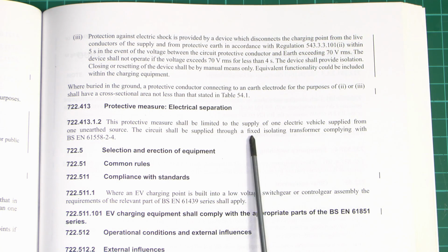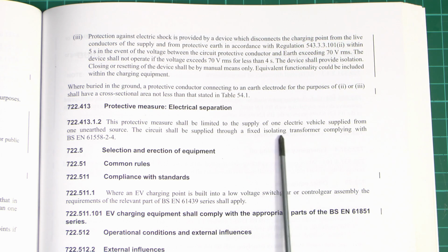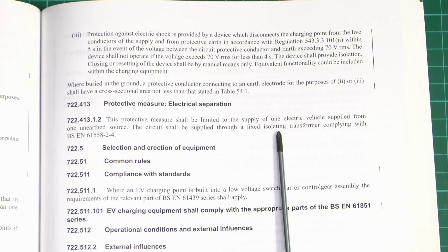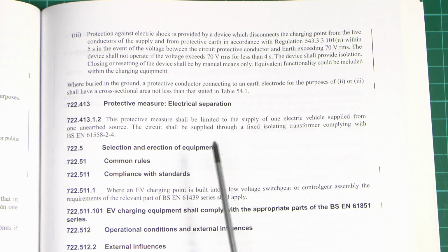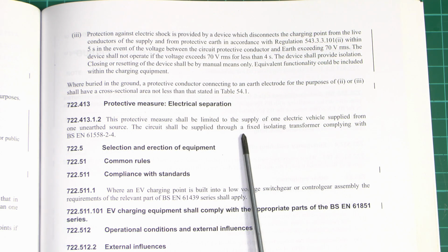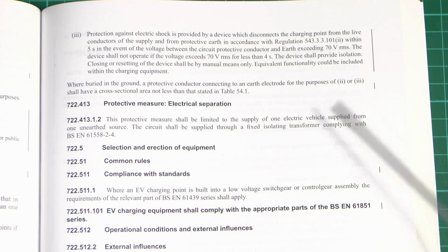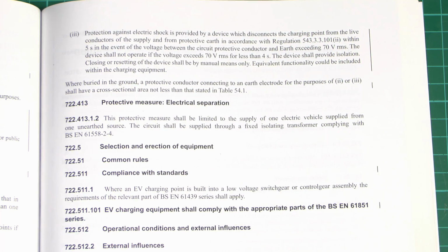The problem here is that an isolating transformer capable of dealing with 32 amps on a continuous basis is going to be a very large and heavy piece of equipment. It's all going to be quite expensive, and quite frankly nobody is going to go for that option, but nevertheless it's an option that's there if you really wanted to use it.